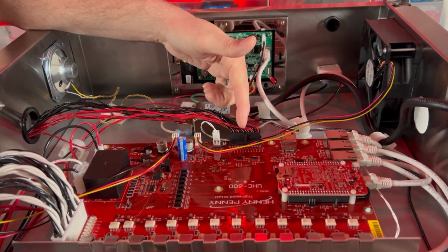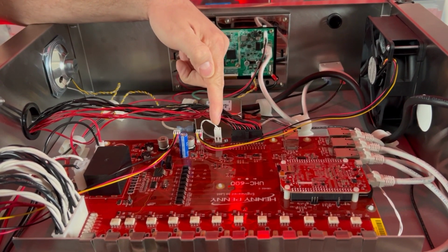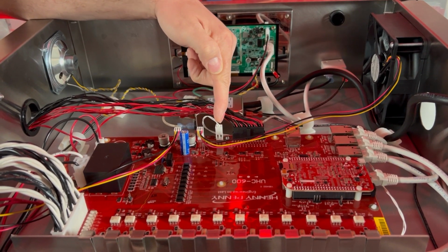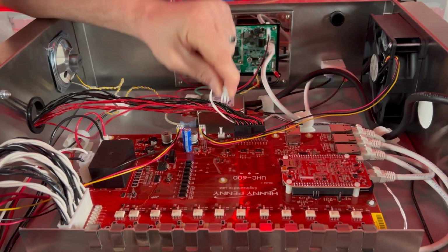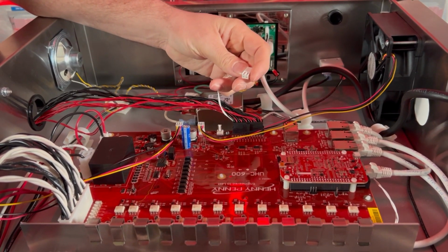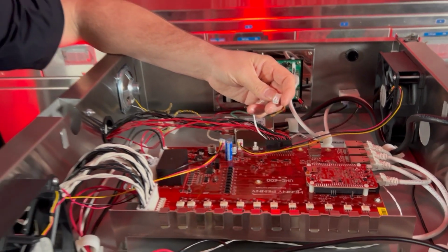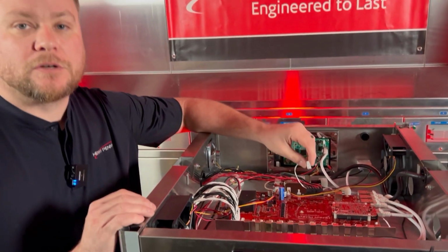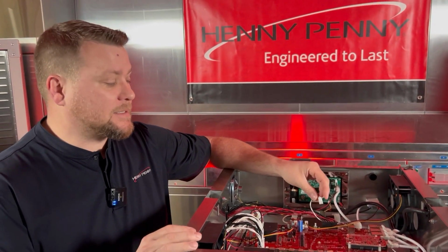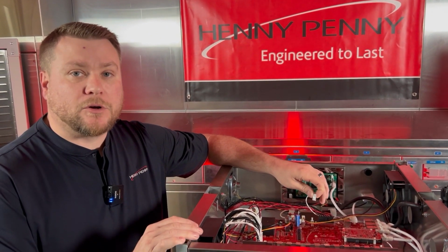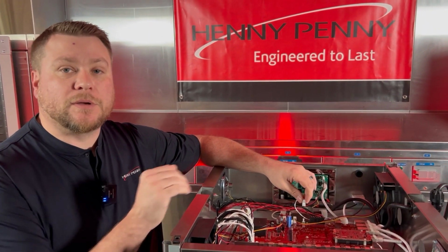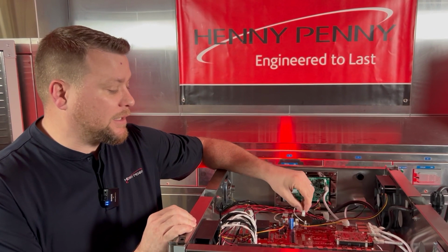But if that checks out well, then we can jump over here to our heatsink probe. We can go ahead and unplug this heatsink probe and then check right here with our meter, checking for an open circuit again. If that tests out fine, then we know our heatsink probe is good. However, if it doesn't, we can replace it because it is a replaceable item.